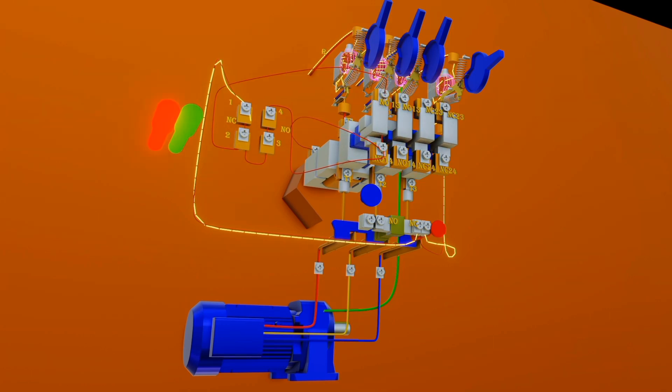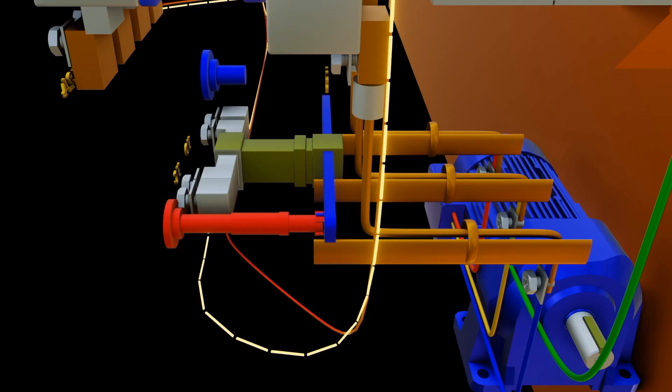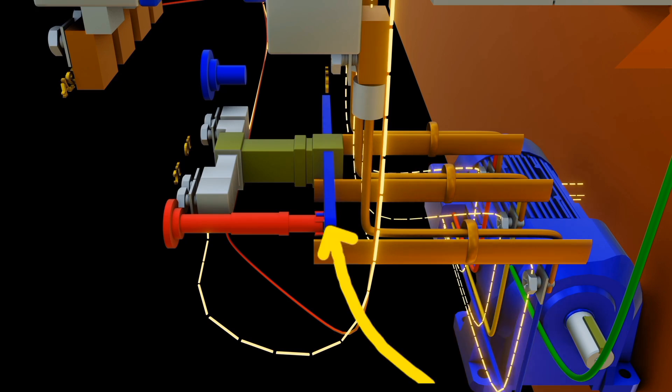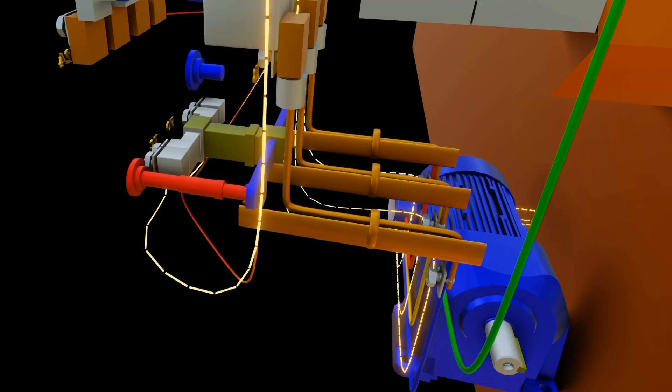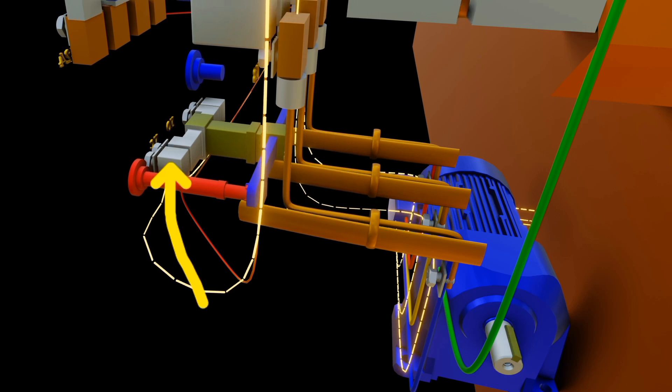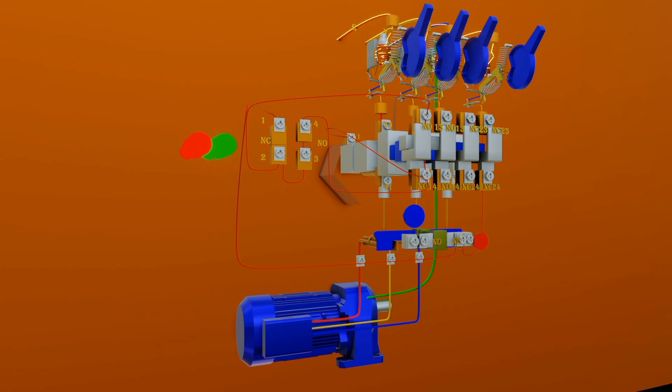But remember that these wires were first connected to normally closed of the thermal overload relay. As you have said before, that if the overload occurs, the bimetallic strip bends moving the contacts so that normally closed opens and normally open closes. This helps in the motor protection against overload that circuit breaker could not sustain.